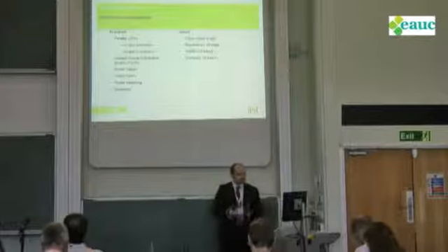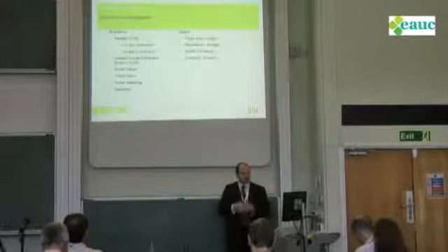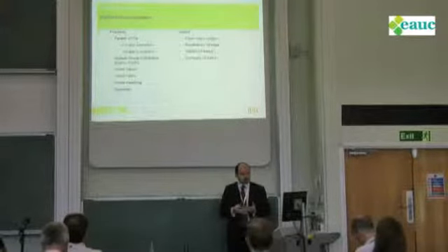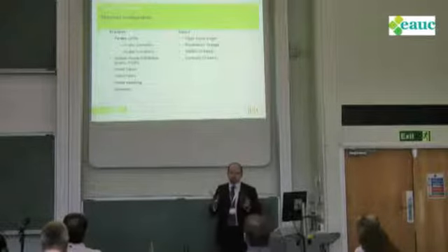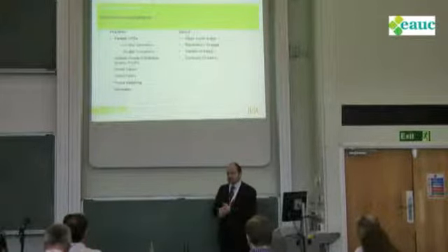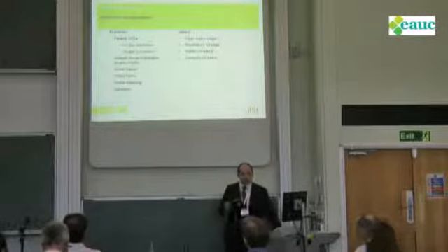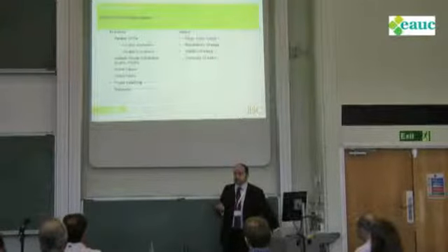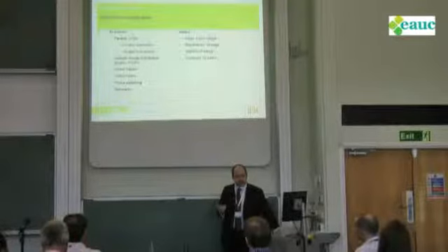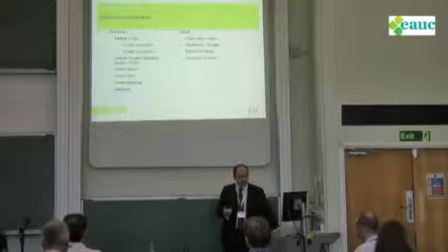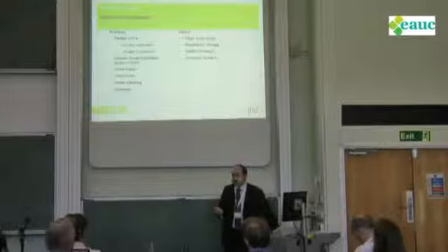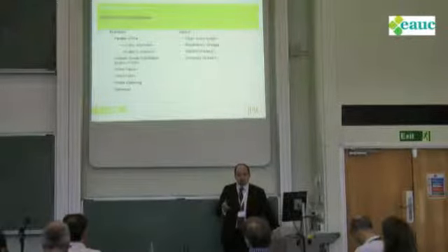In electrical configurations, UPSs, and if you want resilience, obviously you can put parallel UPSs in. Now, there's two schools of thought in terms of efficiency of UPSs. There's a lot of people who tell you that it's okay to use the new eco modes UPSs come with, which means basically they don't interfere with the power coming into facilities so much, so you're not getting a lot of the electrical losses that you might otherwise get. And then you could get 98, 99% efficient UPSs if you choose to go down the eco route.